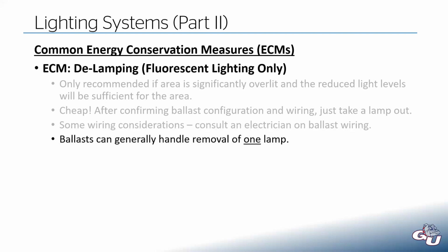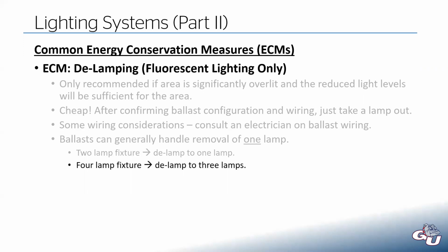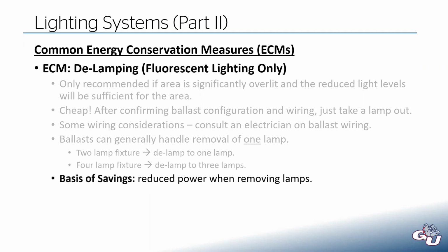Generally speaking, a ballast can handle the removal of one lamp. So it's very common to have a 2-lamp fluorescent light fixture, and you could delamp that down to 1 lamp. But it's also very common to have a 4-lamp fixture, in which case you can go down to 3. Basis of savings here, again, we're reducing the power.